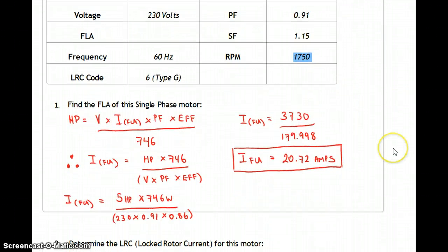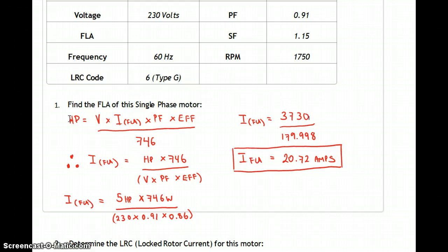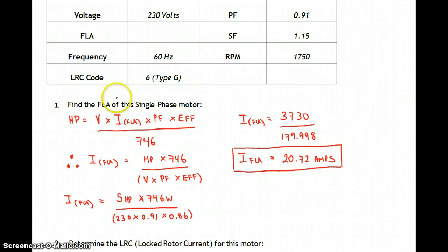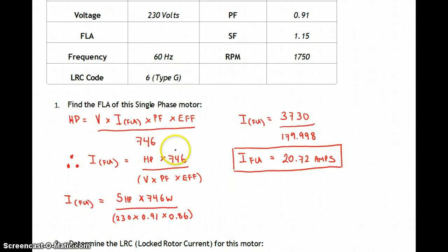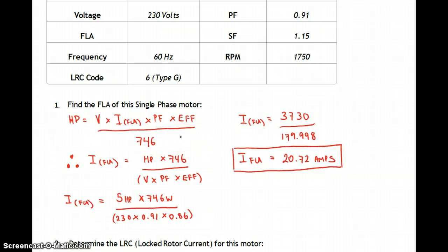The first thing is finding the FLA of the motor. We can reconfigure the horsepower equation — voltage times current gives VA, times the power factor gives wattage, times efficiency, divided by 746 to get horsepower. Reconfigured for current: horsepower times 746 over volts times power factor times efficiency. No root 3 needed here because it's a single-phase motor.